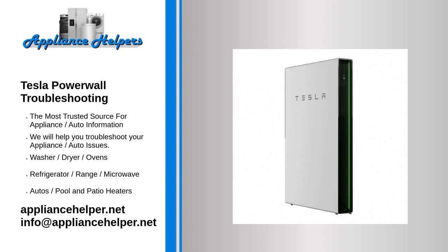Breaker open. The following may indicate that your breaker is open, leaving your Powerwall unable to store energy. You receive a breaker open alert in the app. The LED light on the right side of your Powerwall is not turning on. Note: do not troubleshoot if there are any signs of heat damage, smoke, burning smell, or any other signs of burning to the breaker box. Reach out to customer support if you detect heat damage.